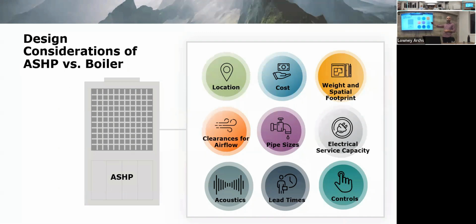Acoustics: they have compressors, so they will make noise. You have to take that into account. And they may cause vibration as well. So the pad will have to have some vibration isolation, similar to your chillers, basically.